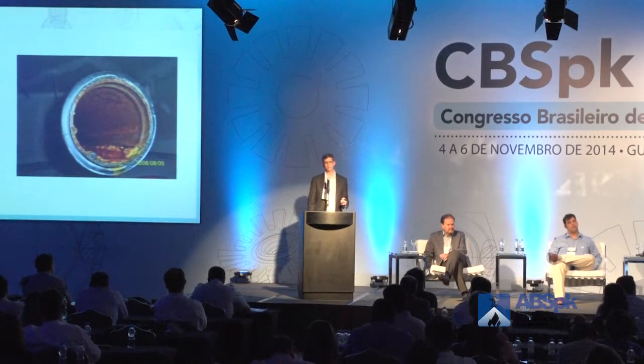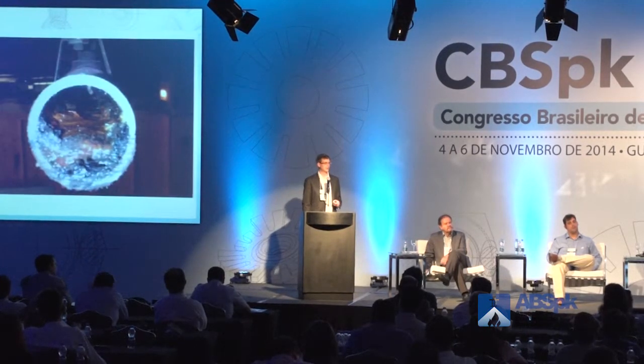So here's some pictures of what dry systems look like with corrosion. This is the beginning of corrosion. I would consider this Class 1, something where it doesn't need to be replaced. As you see, as the corrosion progresses, you see more corrosion deposits, things that need to be replaced. Again, the sprinkler system, or the sprinkler piece of pipe, will need to be replaced. And then you see things like this, where so much corrosion is going on in the inside of the sprinkler systems that the entire system should be replaced because this is prevalent throughout the piping array.